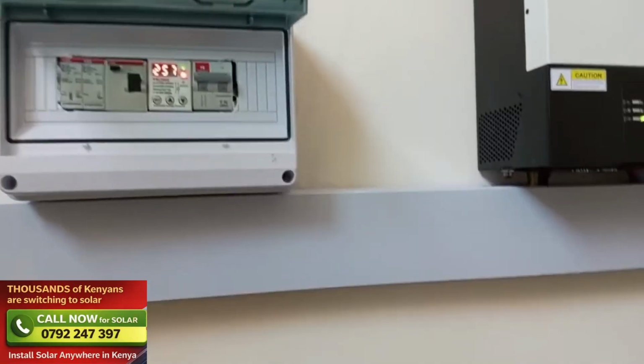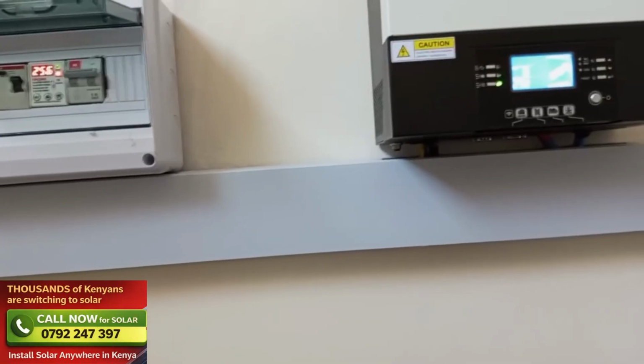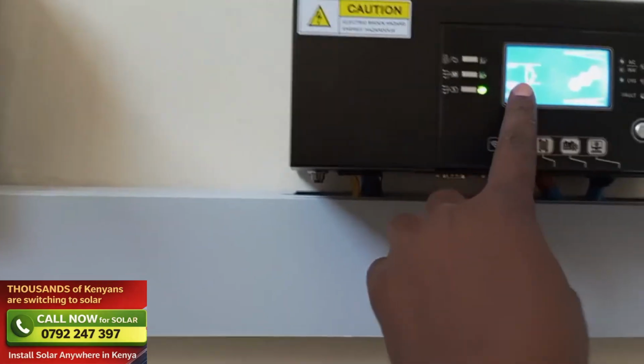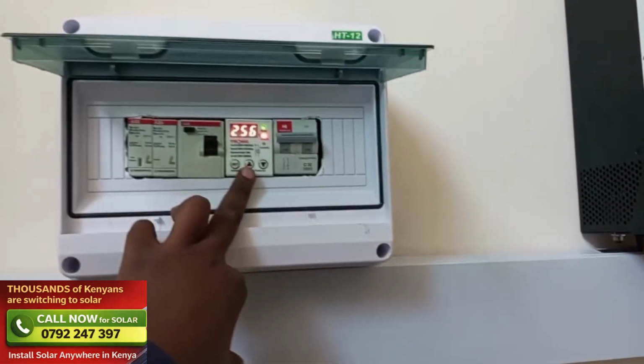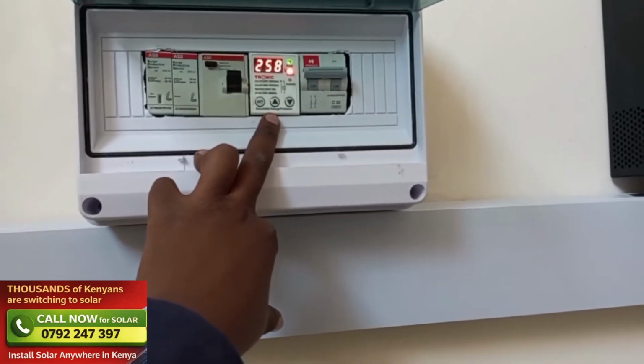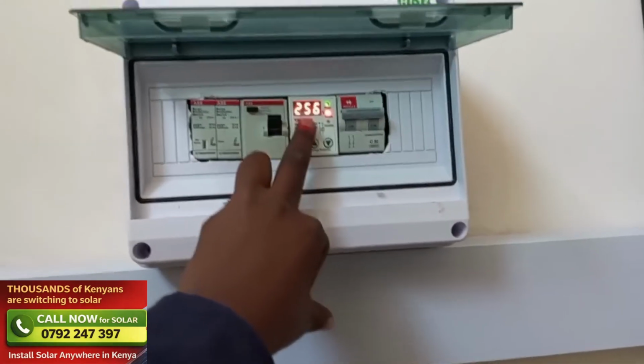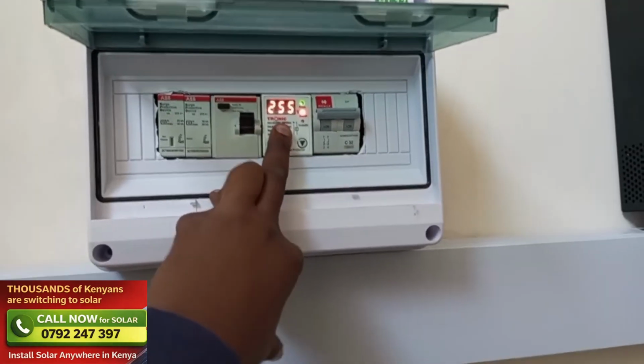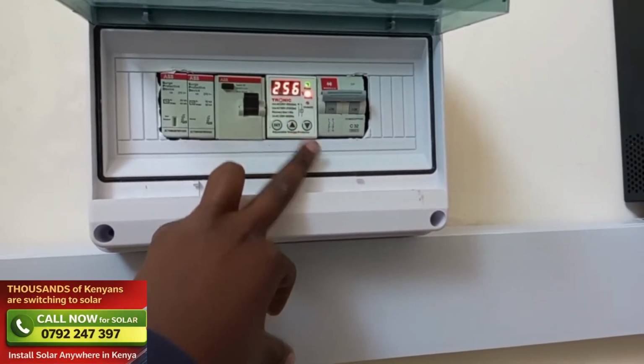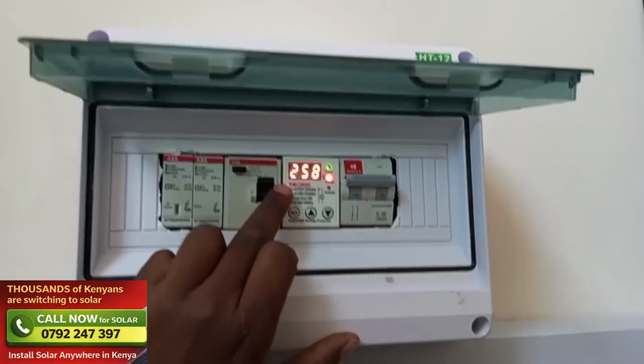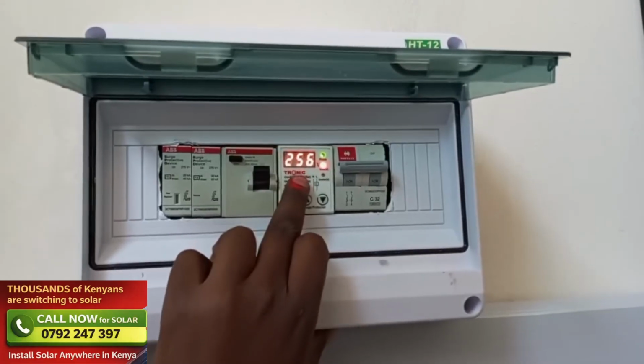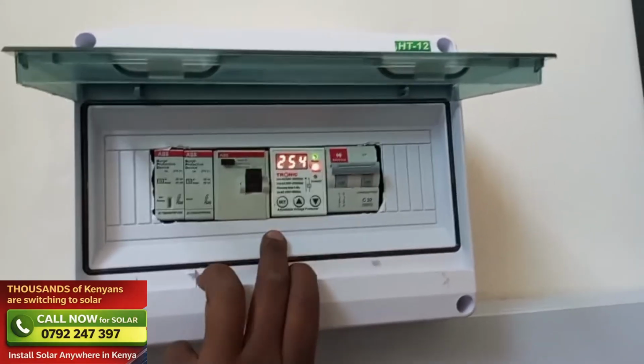As of now, we are not able to see the AC power reflecting on the inverter. The input power is 0 since the incoming power, which is Kenya Power, is above what the inverter needs. Ideally, our voltage is supposed to be in the range of 240, but right now it is at 256, which is not healthy for our appliances. So the system is not able to charge the batteries until the issue is sorted out.